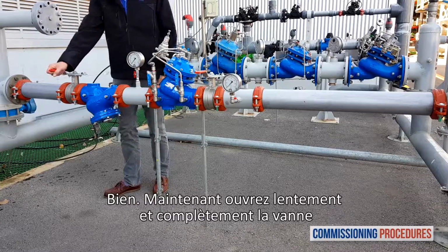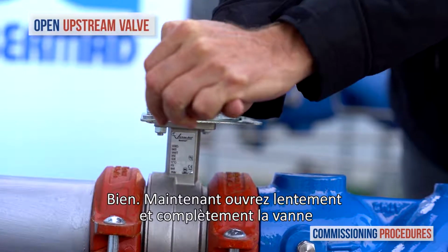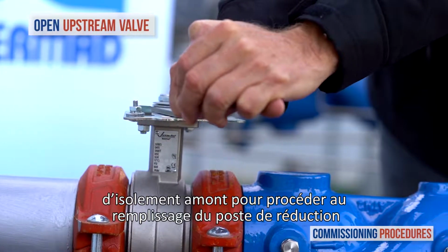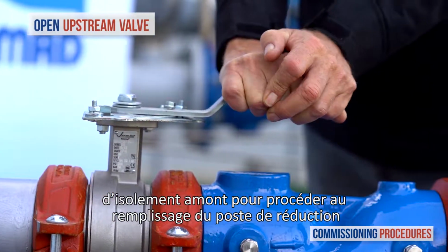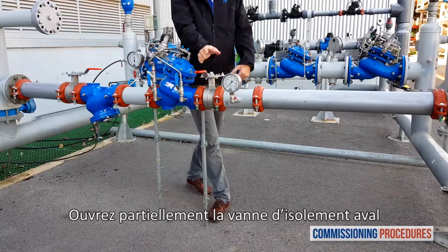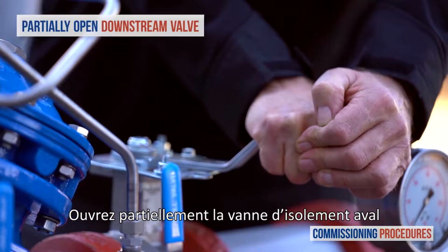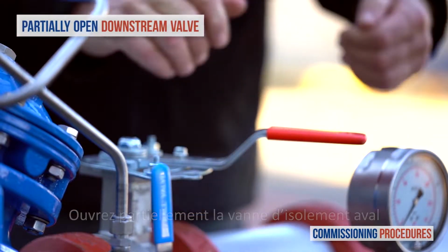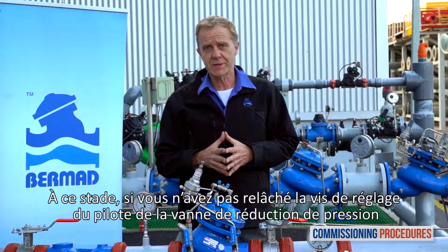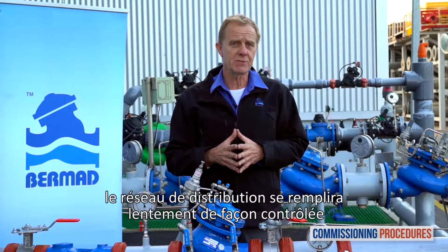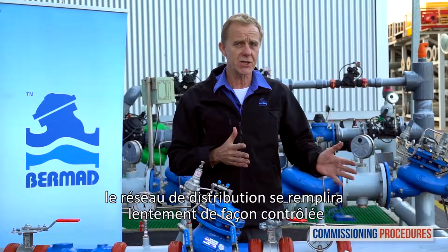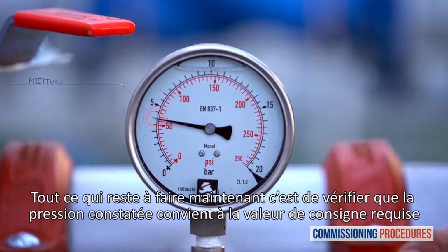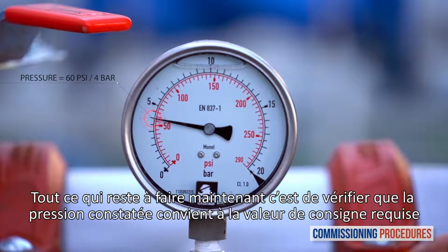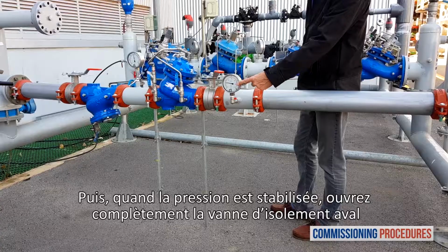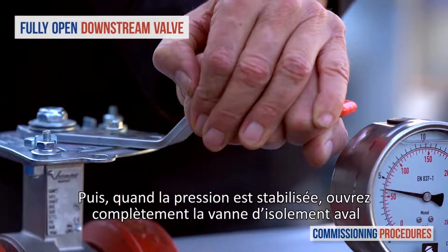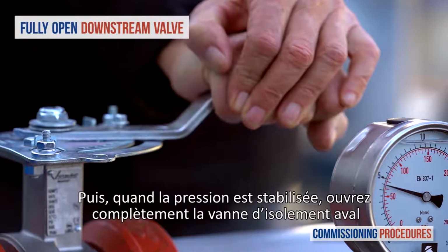All right, now slowly fully open the upstream isolating valve to fill the station with water. Proceed by partially opening the downstream isolating valve. At this stage, if you haven't released the pilot's adjustment screw, the consumer's line connected to the station will fill in a slow and controlled manner. All you need to do now is to check that the downstream pressure is compatible with your requirements. And when pressure has stabilized, continue to fully open the downstream isolation valve.